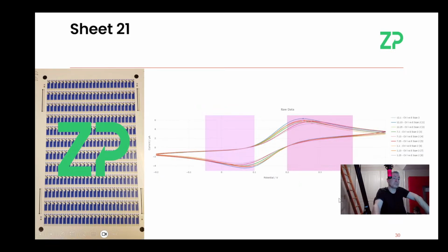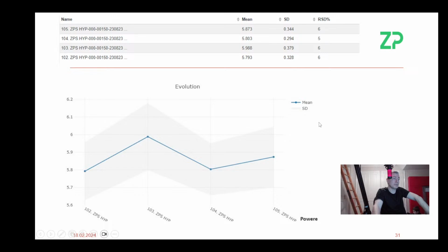characterization of materials before they're shipped, but we make sure that we characterize it before it's shipped so that we can understand the peak height through a batch. So here I can see 5.8 peak heights on those voltammograms on sheet 102. On sheet 103 I can see the peak height is about 5.99, if I can call it that. I can see the peak heights.